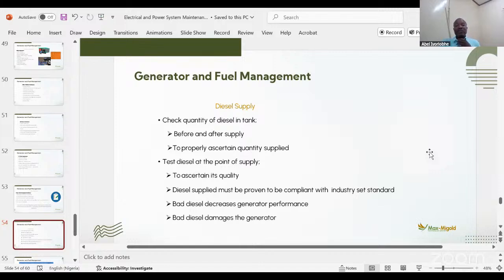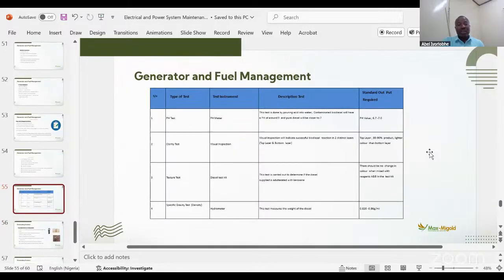We have values that we look out for - density, for example. See the table showing the range. With litmus paper, when you dip it in, red litmus becomes pink, or pink becomes red, if there is water inside. The density most of us are used to is around 0.845, 0.83, and so on. It must not fall below a certain standard, around 0.82 grams per cubic centimeter.